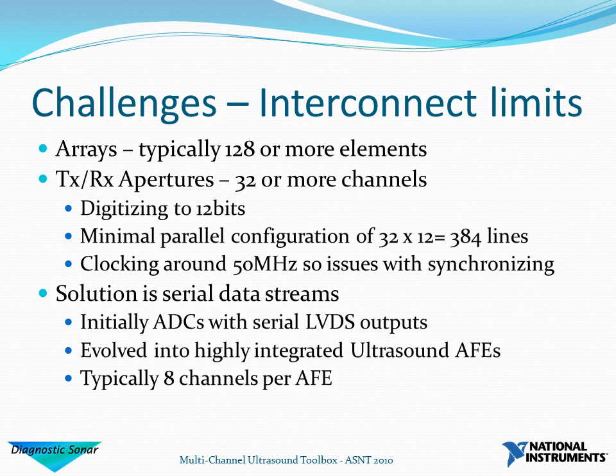The solution is to use serial data streams. Initially this was done by the semiconductor industry for A-to-D converters at high data rates, using serial low-voltage differential signaling outputs. Largely driven by the medical market, these were expanded into what's referred to as ultrasound analog front ends, which have analog swept gain capability, some filtering, and A-to-D conversion incorporated into the same device. Typically an analog front end includes 8 channels, although current ones deal with 16 or more.